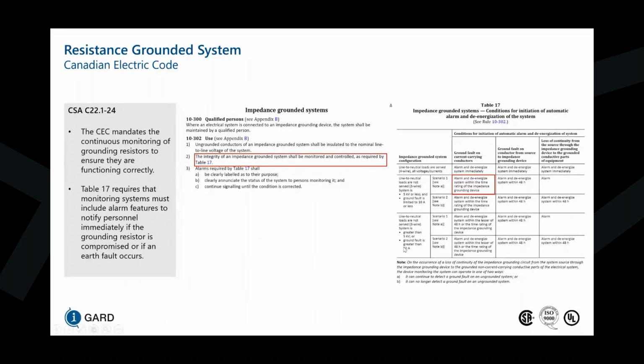Now in the third row, we have our low resistance grounding, where if your system is greater than 5 kV or ground fault is greater than 10 amps, it indicates to alarm and de-energize the system within the lesser of 48 hours or the time rating of the impedance grounding device. But typically, most consultants are tripping on first fault and using a 10-second or 60-second rated resistor.